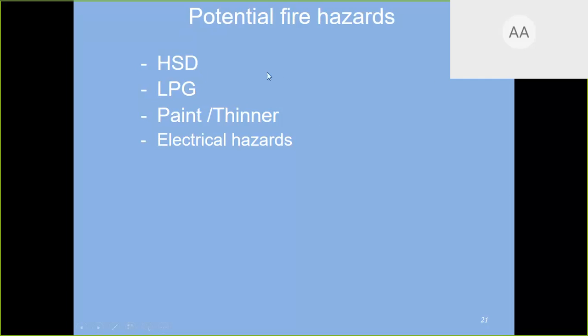What is the countermeasure for this? One is HSD. For HSD, I have already explained the earthing system. If you install the earthing system, there will be no fire in the HSD tank, whether loading, unloading or transfer. Every place you have the earthing system. Second is LPG. For LPG, if we have installed an LEL detector, there will be no fire because the LEL detector will give you an alarm before it reaches the LEL level.